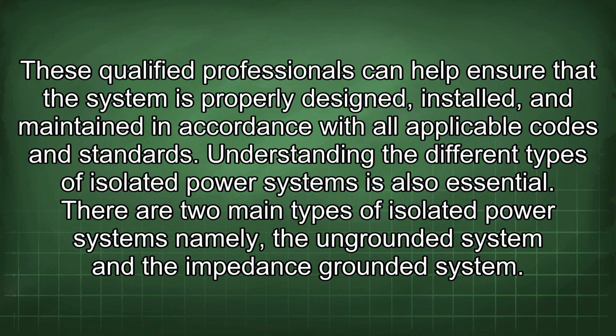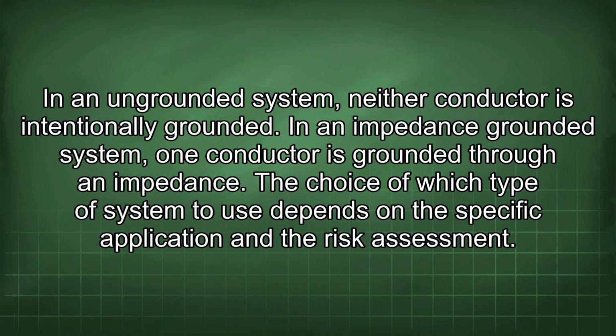These qualified professionals can help ensure that the system is properly designed, installed, and maintained in accordance with all applicable codes and standards. Understanding the different types of isolated power systems is also essential. There are two main types of isolated power systems, namely the ungrounded system and the impedance-grounded system. In an ungrounded system, neither conductor is intentionally grounded. In an impedance-grounded system, one conductor is grounded through an impedance.